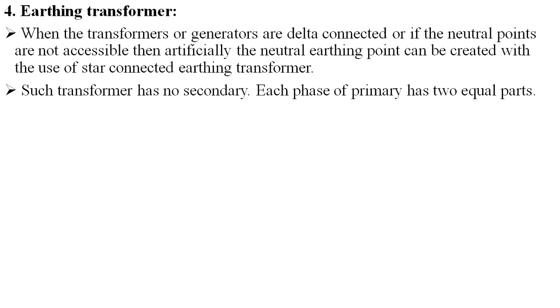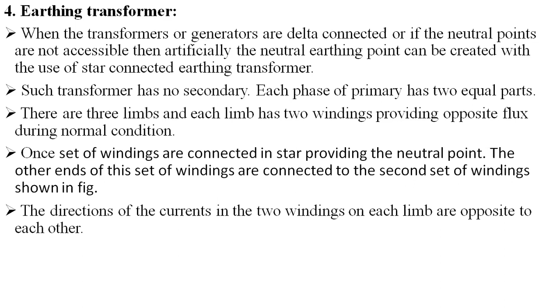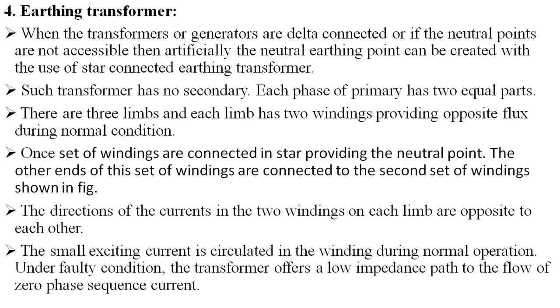So once a set of windings are connected in star providing the neutral point, the other ends of this set of windings are connected to the second set of windings, and the directions of the currents in the 2 windings on each limb are opposite to each other. And a small exciting current is circulated in the winding during the normal operation. Under faulty condition, the transformer offers a low impedance path to the flow of zero phase sequence currents. So the value of the fault current is limited in some cases by the use of a resistor in series with the neutral earthing connection.